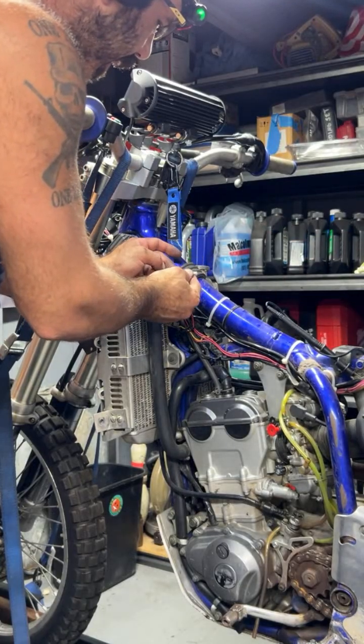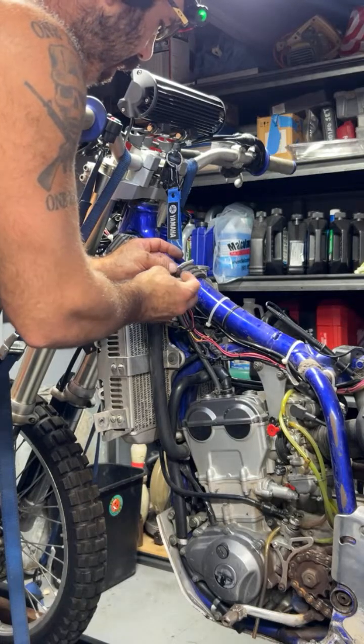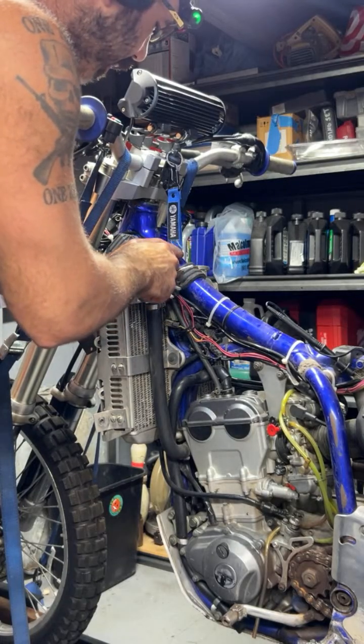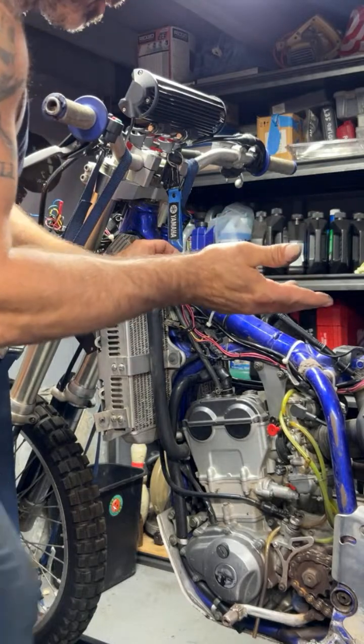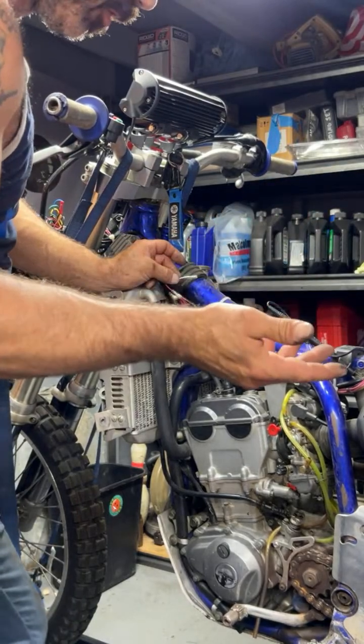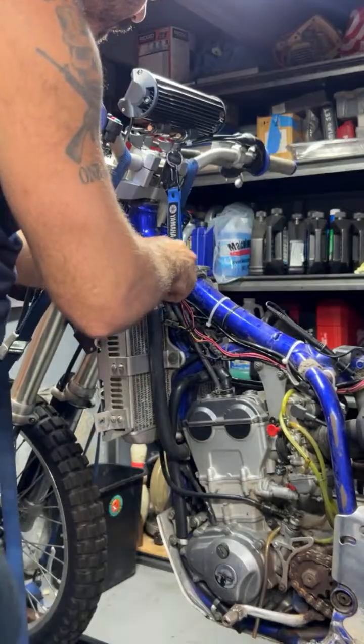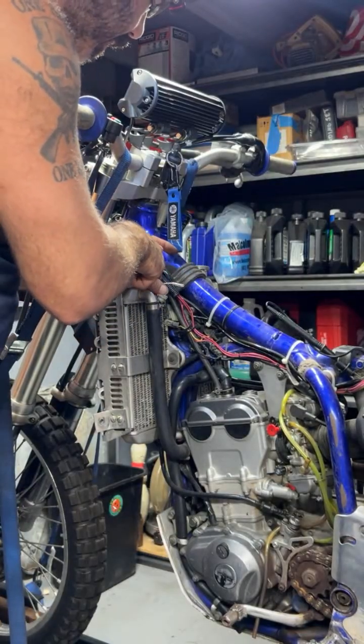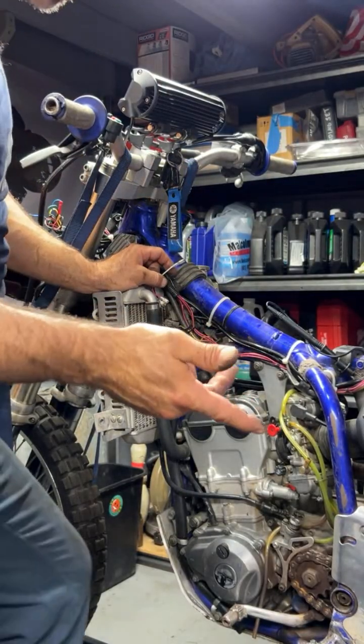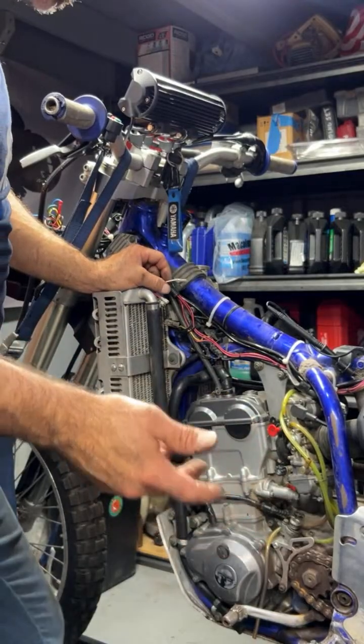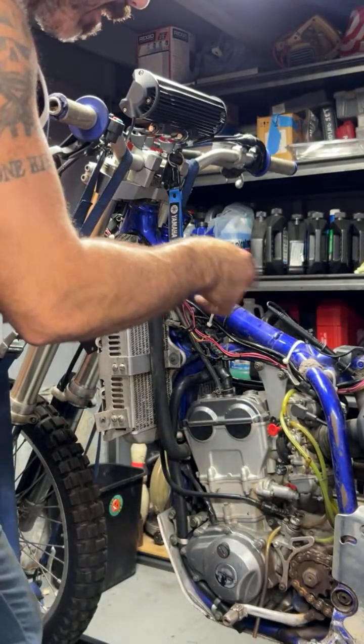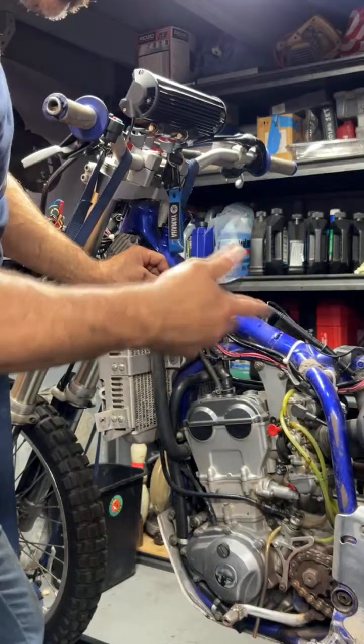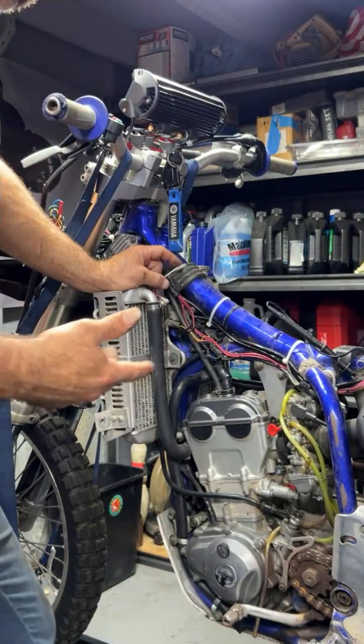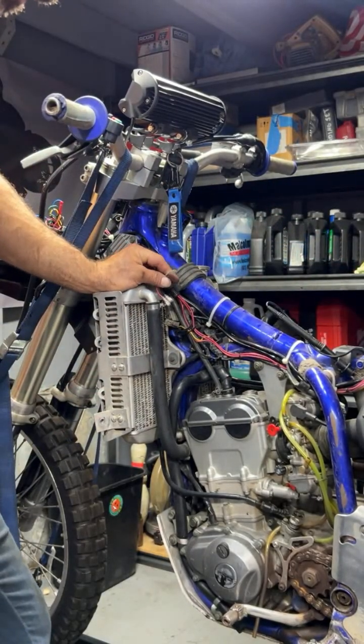And then this right here has resistance to ground, which if it's wired correctly, I don't know, I don't have actual ohm readings to go off of, but typically this is a hot right here that's going to flow through some type of resistor like an LED light bulb or an incandescent light bulb to ground. So that's why I have resistance to ground, it's not open and I'm not getting direct power. So that tells me there's a good chance that this is working.